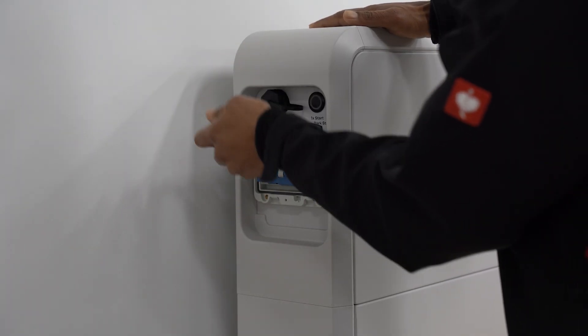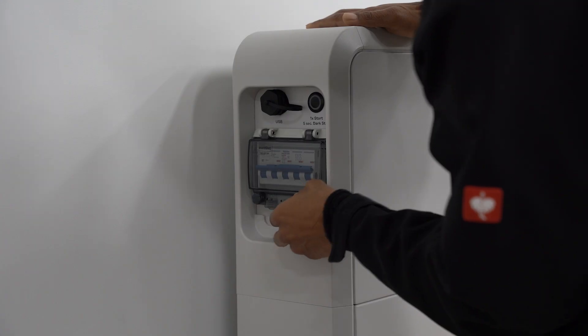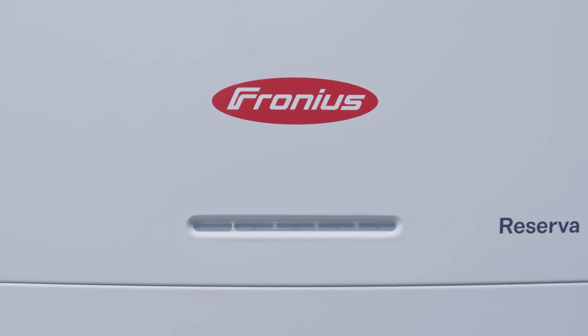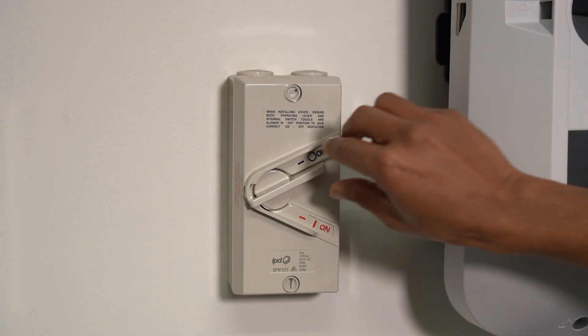Turn on the Reserva by flicking up the main switch and then press the start button once. You will see the left LED on the front flashing green. Then turn on your Gen24 Plus by switching on the DC isolator and the AC isolator.